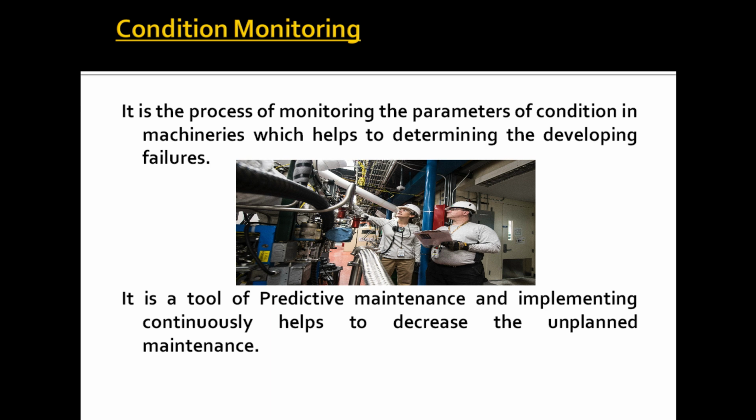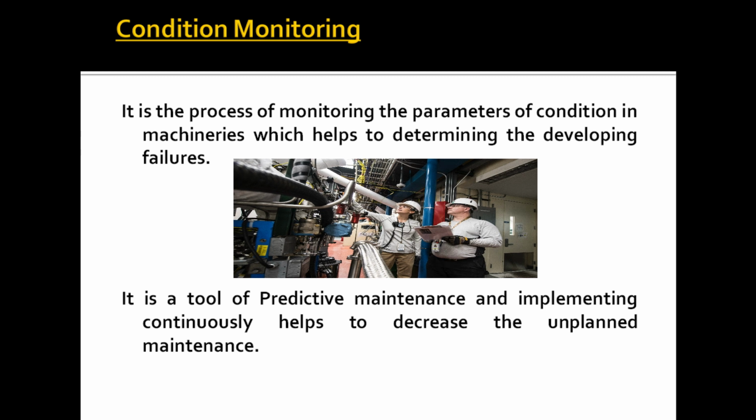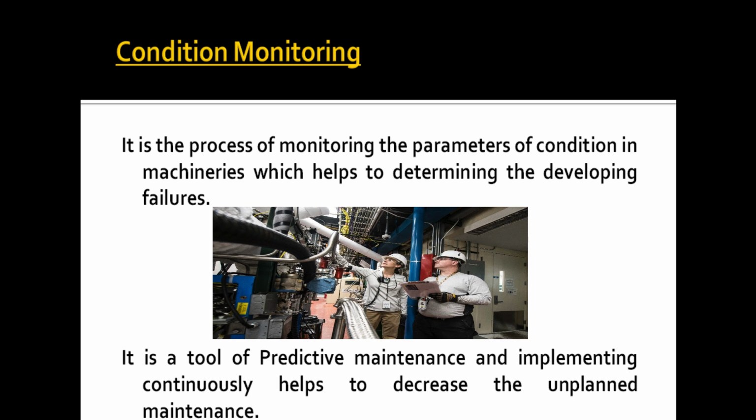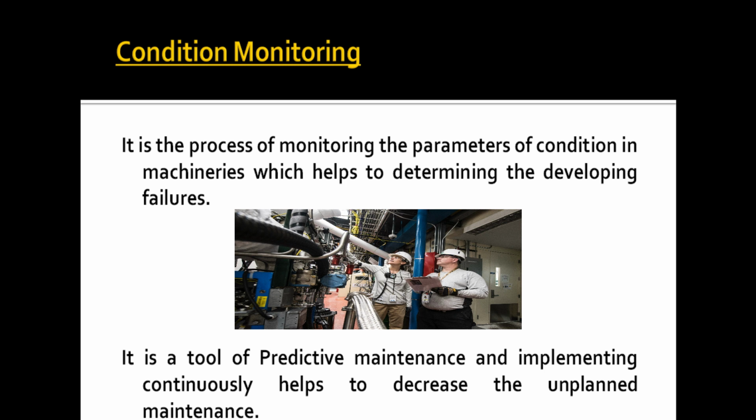In simple form, we know that during long runs of operation or inappropriate operation, machinery gets exposed to high temperature, pressure, cyclic load, or hostile environment, due to which fatigue, residual stress, and sometimes even microstructural degradation form. Such abnormal conditions are generally detected through different parameters like vibration, noise, temperature, infrared radiation, etc. The data obtained from condition monitoring is well analyzed, and depending upon the requirement, maintenance activities are carried out. Here, the critical components are well handled and unplanned maintenance decreases.